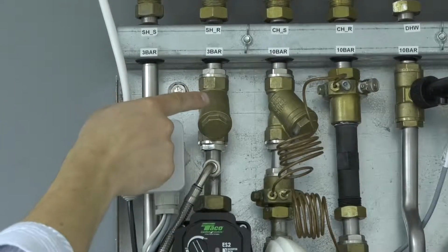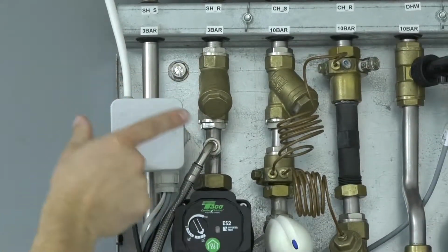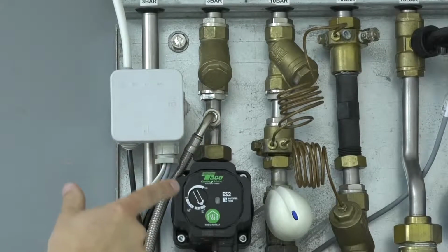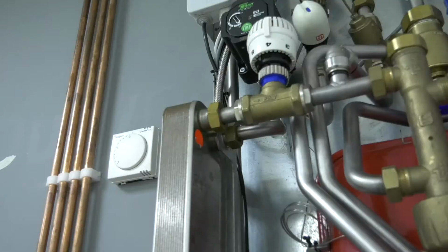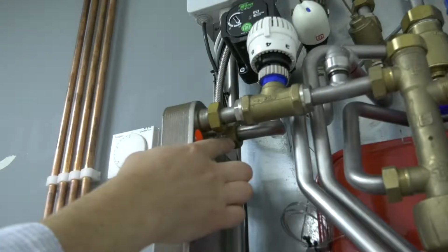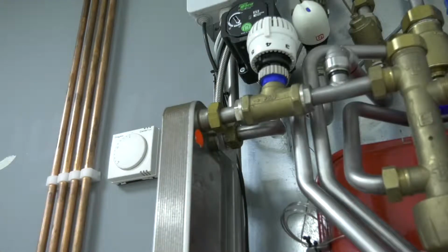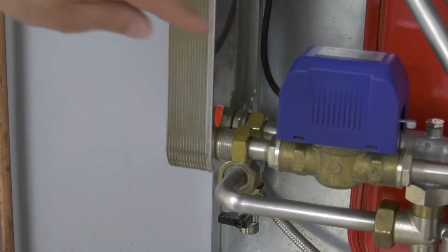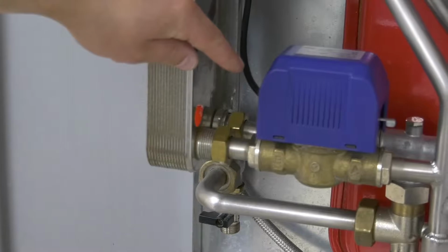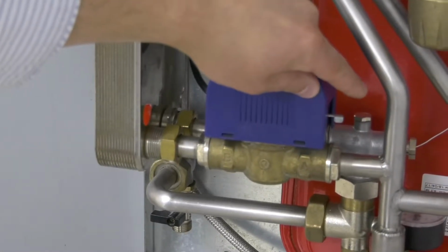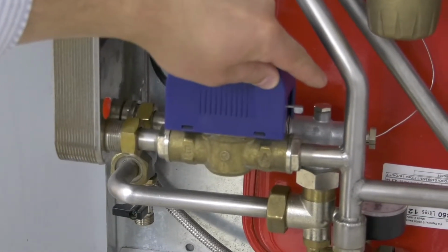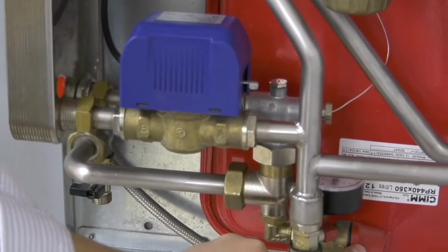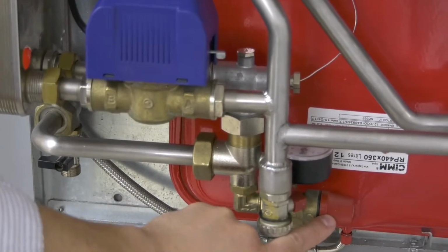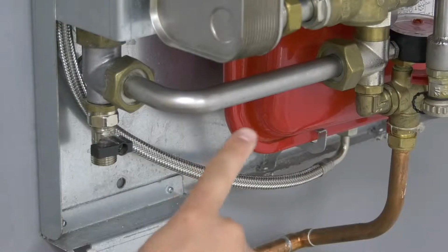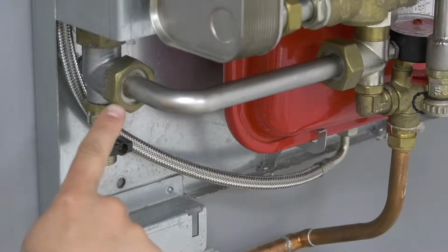Following down the secondary return, there is the strainer, vessel connection, and pump. This leads down to the plate heat exchanger heating secondary inlet. And here you'll see the plate heat exchanger heating secondary outlet, a temperature sensor probe, and the pressure relief valve. Here is the secondary return pipe with a port for the filling loop.